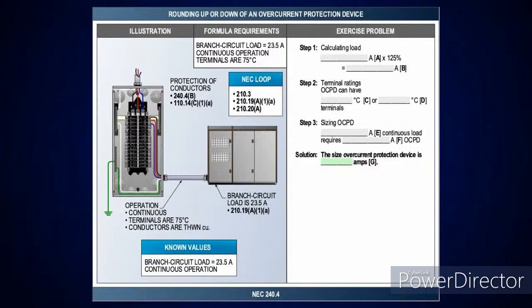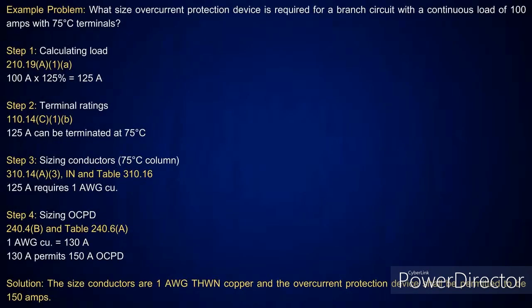Now, here's where I'm going with a branch circuit. I'm getting up in the amperage. Okay? What you're going to see is very simple, but we did something a little bit different here to make you think about this. Now, you've got a continuous load of 100 amps with 75 degree C terminals. So we'll just look at doing the conductor. You take it at 125%. That's 125 amps, and it can be terminated at 75 degrees C. Now, if I go look at Table 310.16 and pick up the 75 degree C column, it's going to tell you need a number 1, which is good for 130 amps.